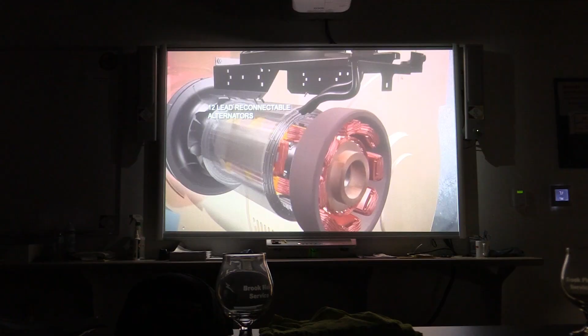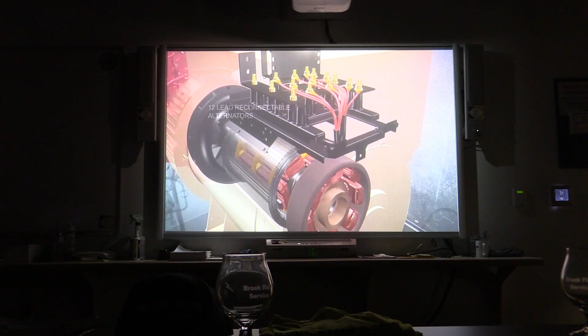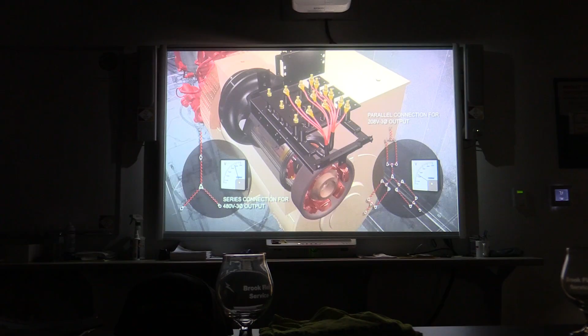Doosan mobile generators also include alternators with 6 coils wound into the stator, providing 3 voltage sources, or phases. Because each phase combines 2 coils of wire, the sources can be connected in series for high voltage applications or in parallel for low voltage needs.